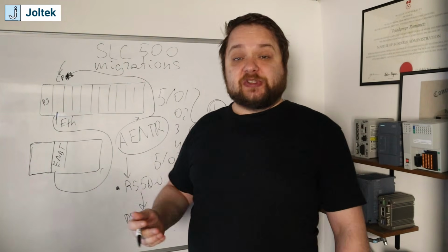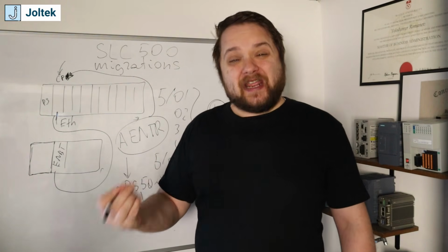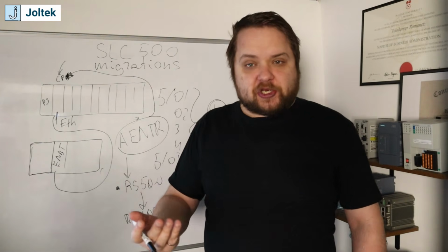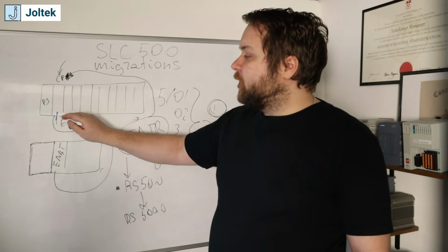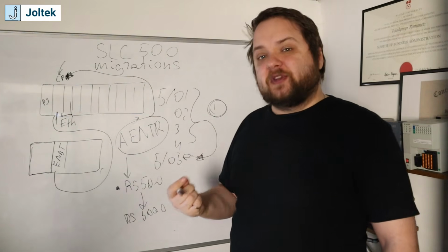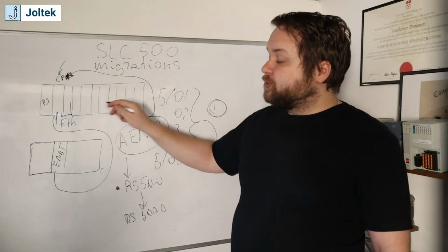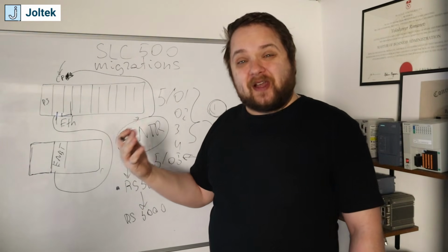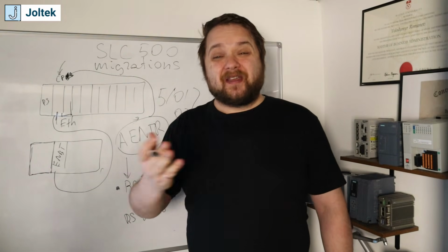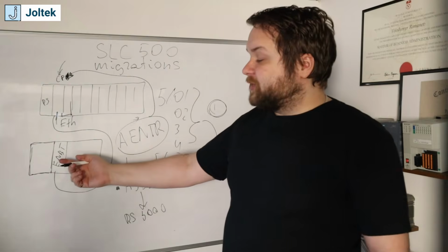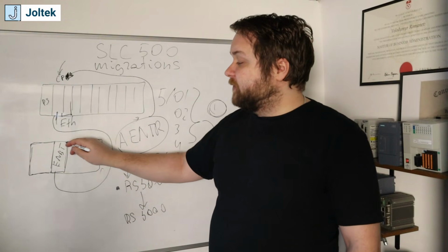Of course, this PLC, chances are, is already running or controlling some kind of an area. So you need to double check, does it have enough memory? Is it able to accommodate all of the cards? So this is the complexity of this migration. Once you review the program, there are going to be different modules inside of the chassis, and it is possible that some of those modules will not be compatible with the RSLogix or Studio 5000 version that is running inside of this PLC.